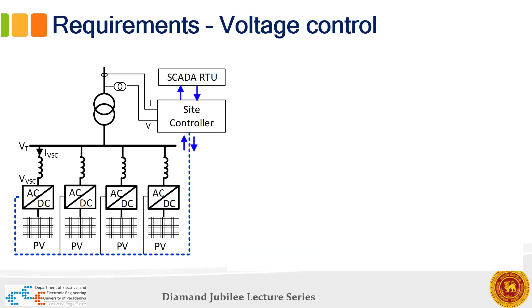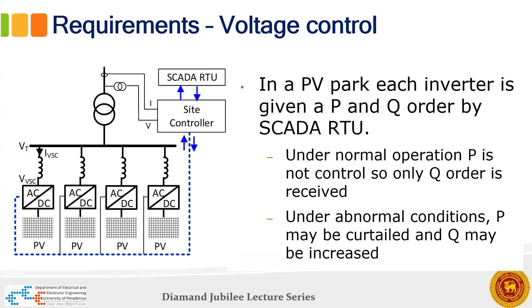For example, in a large ground-mounted solar plant, you definitely need a site controller to send what kind of reactive power requirement needs to come from each inverter, depending on how much capacity is available in the inverter, and also depending on the requirement specified in IEEE 1547.